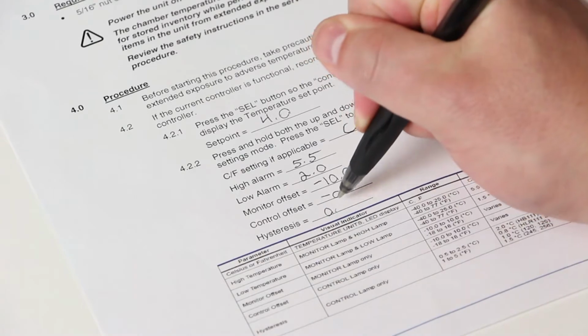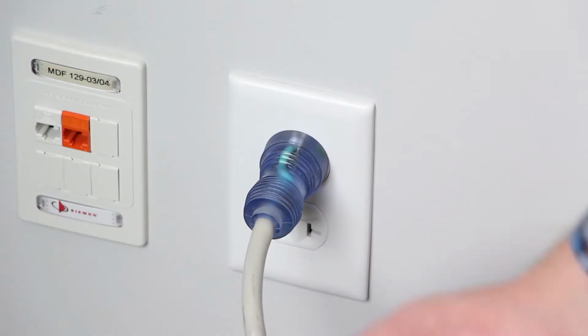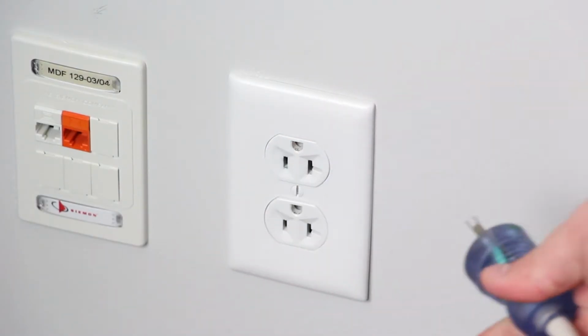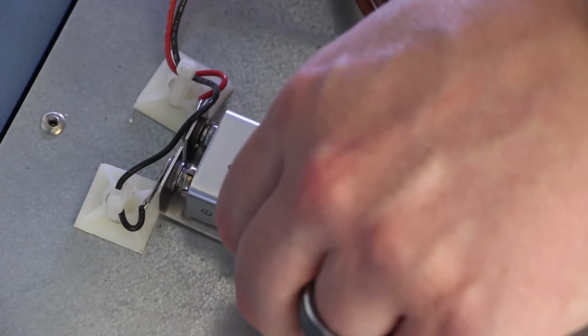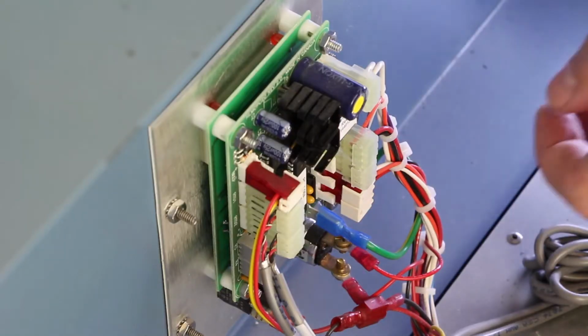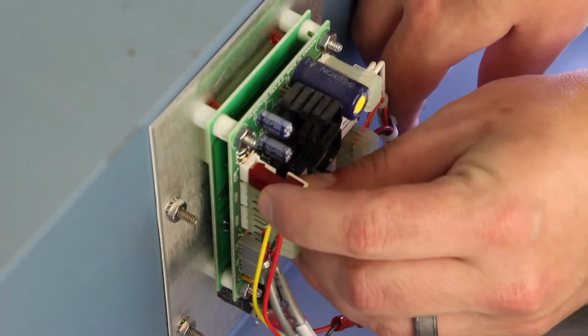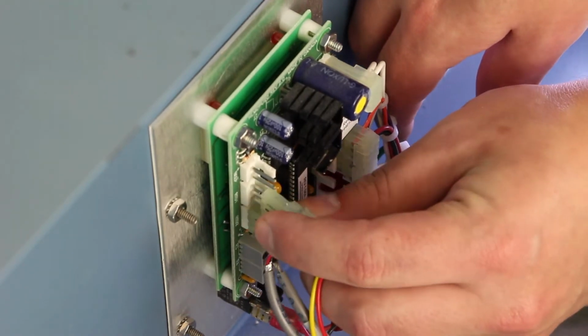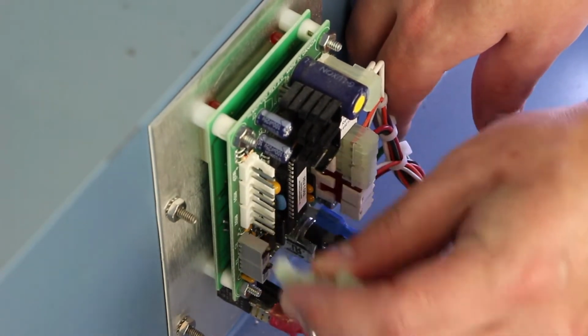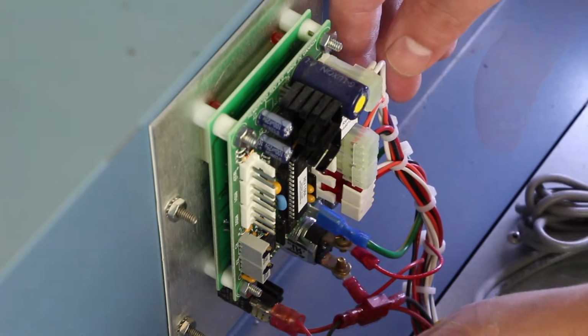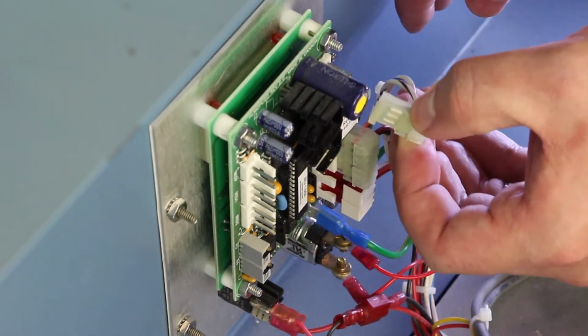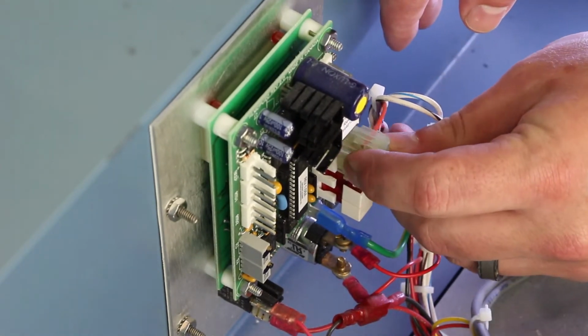After writing down the current settings, remove both main power and the backup battery to power the unit down. Make sure to note the location of the wire connectors and transfer them over to the same connections on the new controller as you remove and replace. Taking a picture or writing down the wire locations is a helpful tip when replacing components.